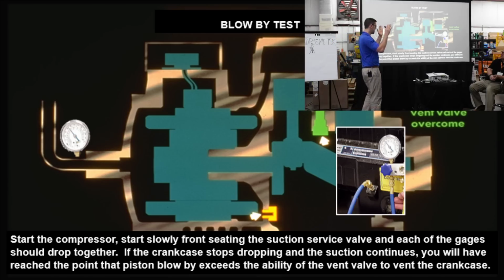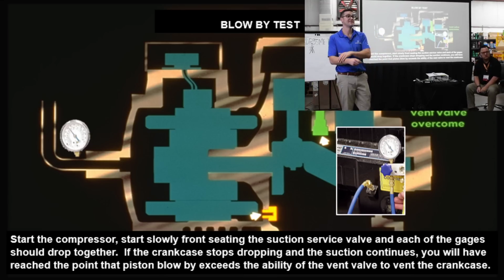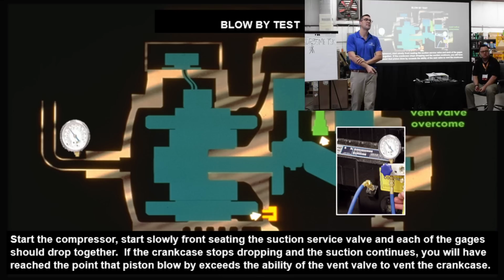Okay, so you'll watch the gauge just here. If the crankcase stops dropping and the suction continues, you reach the point where the piston blow-by exceeds the ability of the vent valve to vent to the crank, to the body. That's one problem, but now you also have potentially another issue. Your pistons obviously warp. Oh yeah, you pull off the head and you'll see it. Yep. So now you have more, and then you would chase it back.